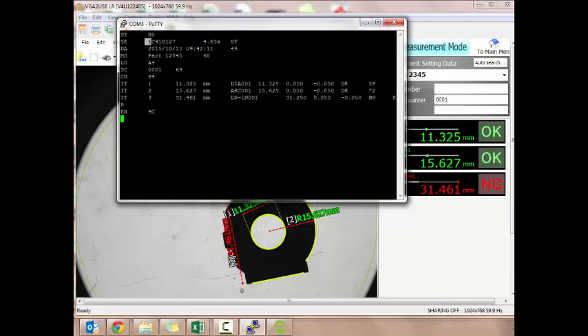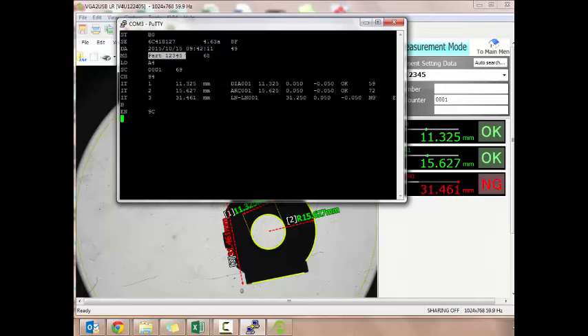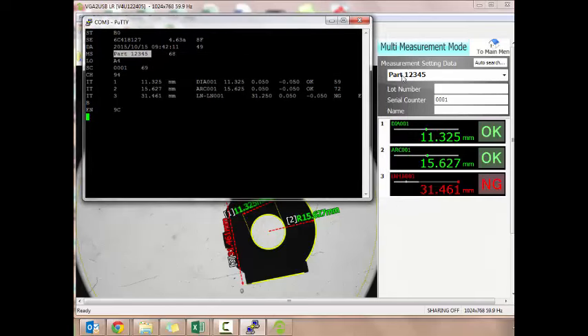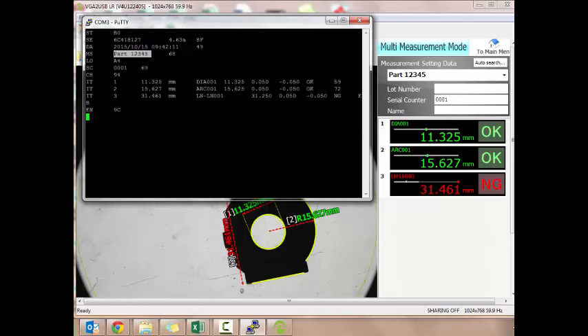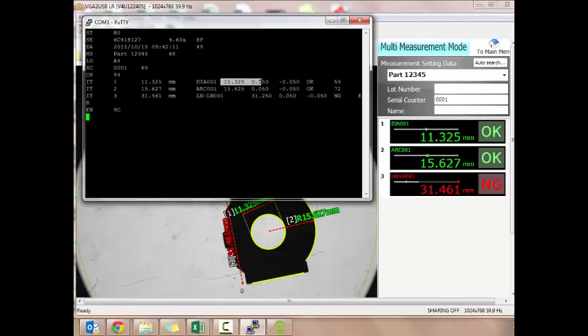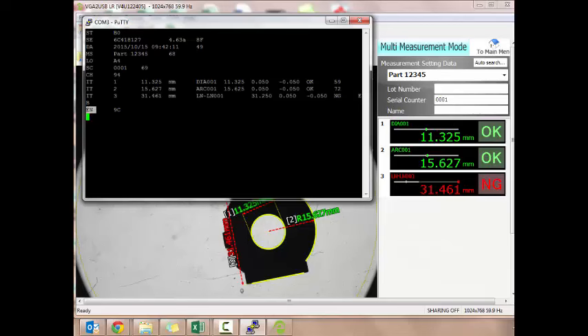What we have here: ST is start. SE is the serial number of the IM system itself. DA would be the date and the time. MS stands for measurement settings, the name of the program. If you'll notice here the program's called part 12345. There's the program name. LO is lot number. SC is serial counter. CH is where the name will go, that's character. IT is item, and here's your values. 11.325, diameter 001. This is the nominal value, upper limit, lower limit. And then here's where your OKs and no goods show up. In this case, I have two OK and one no good part. It then ends with EN for end.